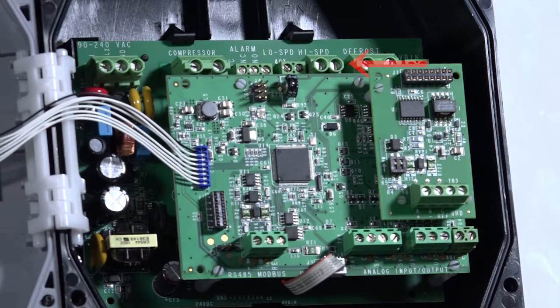The third relay is used to cycle the evaporator fan on and off. The fourth relay is an auxiliary relay. It can be used to cycle the low speed of a 2-speed evaporator fan on or off. It can also be used to turn on a light or other such device. The last relay is the alarm relay. It can be connected to a strobe or annunciator to indicate that an alarm condition has occurred.